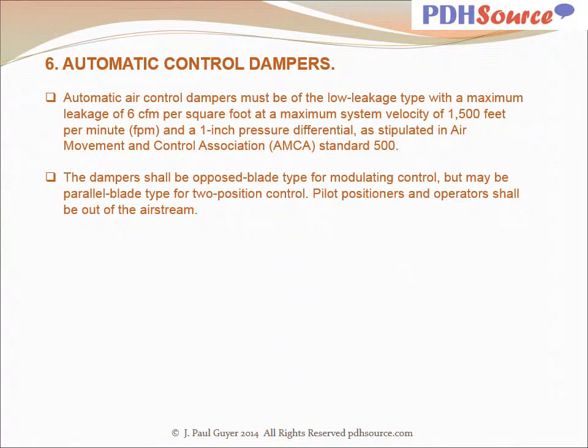Automatic air control dampers must be of the low leakage type with a maximum leakage of 6 CFM per square foot at a maximum system velocity of 1,500 feet per minute and a 1-inch pressure differential as stipulated in AMCA, Air Movement and Control Association Standard 500. The dampers shall be opposed blade type for modulating control but may be parallel blade type for 2-position control. Pilot positioners and operators shall be out of the airstream.